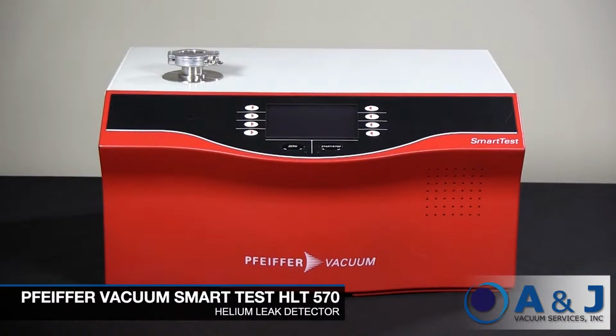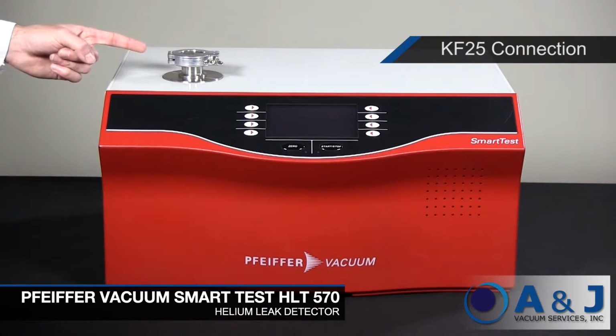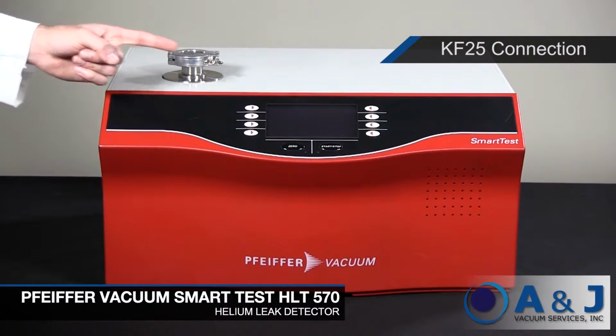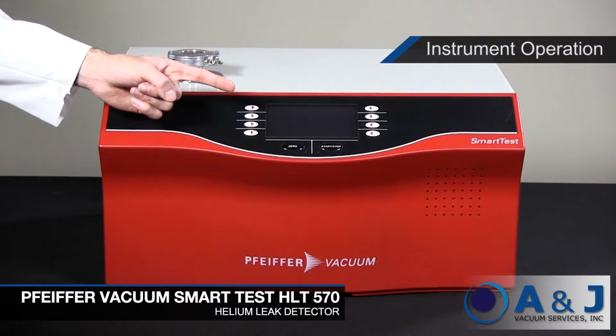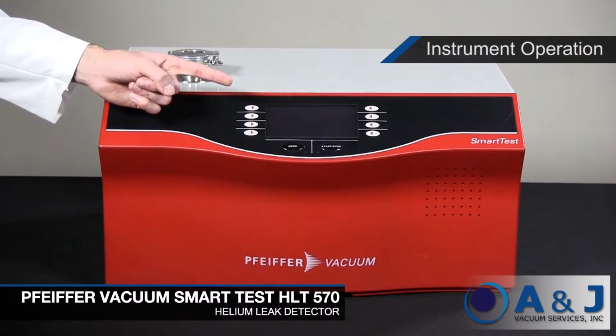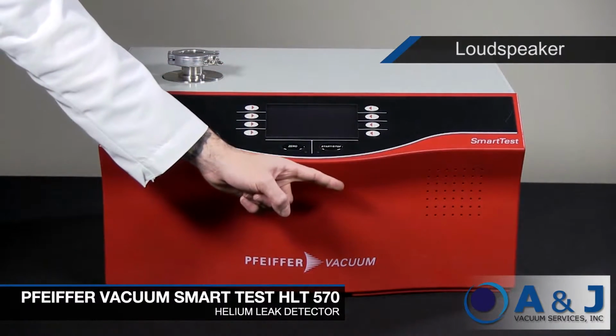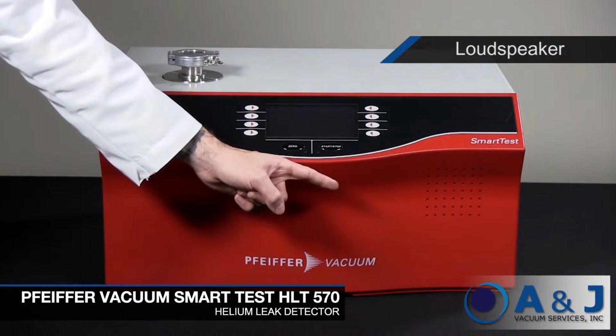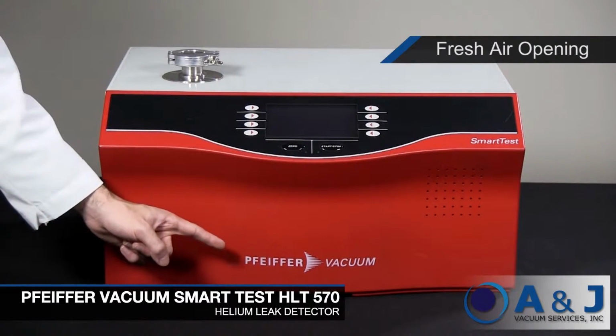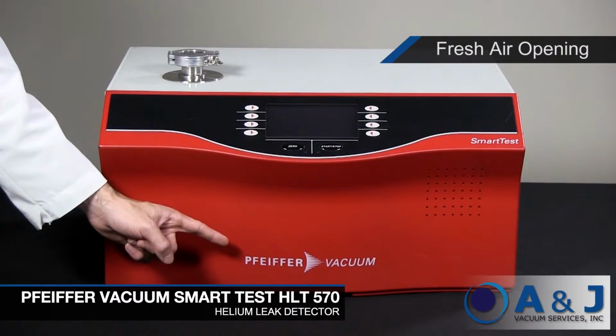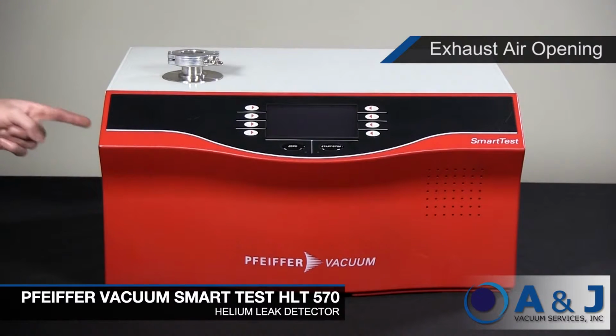The HLT 570 features the test connection, which is a KF25 connection for connecting test objects. The instrument operation is the section dedicated to the display and operation interface. This is the loudspeaker housing, which emits audio signals when testing. The fresh air opening is the opening in the housing for fresh air supply. And on the left is the exhaust air opening, which is the opening in the housing for exhaust air discharge.